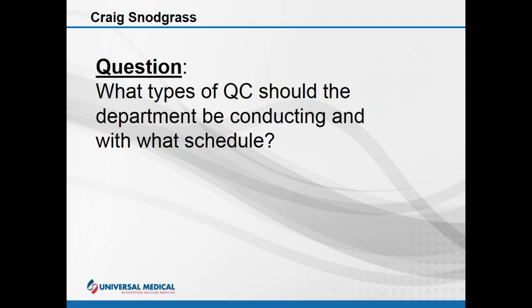The main thing when doing these QC checks is to do them the same way each and every time. For instance, if you're using spacers like a cup or glove boxes to place between the collimator and the cobalt sheet source when doing an extrinsic, try to place them the same way each day. Or if you're radiusing detectors together to a certain position, try to put them in the same position each time.